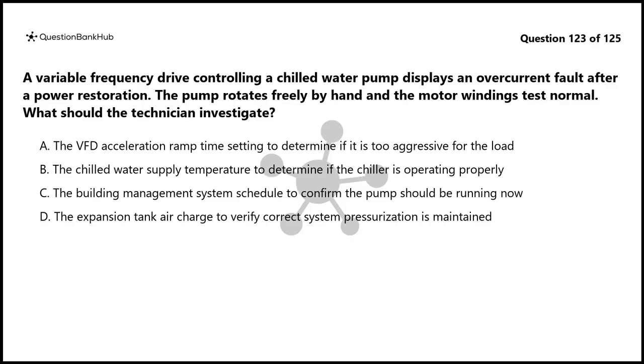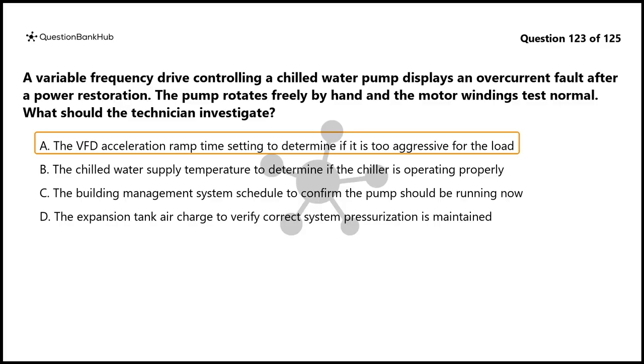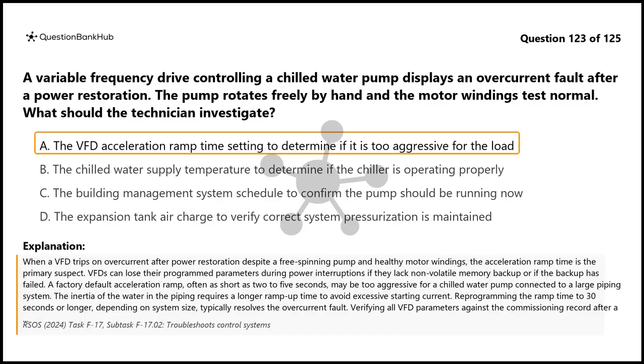The correct answer is A. When a VFD trips on overcurrent after power restoration despite a free spinning pump and healthy motor windings, the acceleration ramp time is the primary suspect. VFDs can lose their programmed parameters during power interruptions if they lack non-volatile memory backup or if the backup has failed.